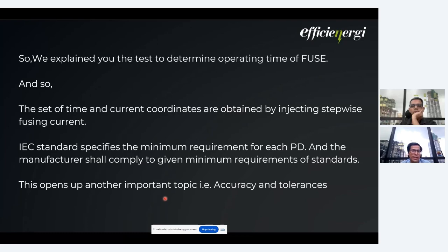We will explain the test that is carried out to determine the operating time of the fuses. On similar grounds, the test is done for all the protecting devices. We will have a different test setup, but the concept behind testing and producing the TCC is the same. This gives a set of time and current coordinates. Again, we inject different fusing currents and note down the related operating time. This is done in multiple steps, and then the final TCC is given by the manufacturer.